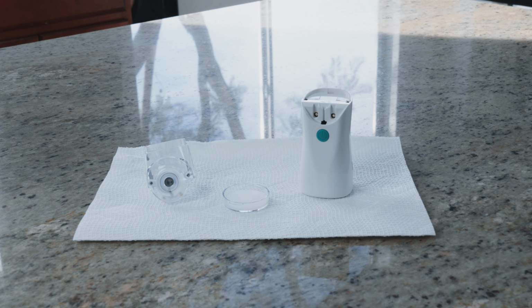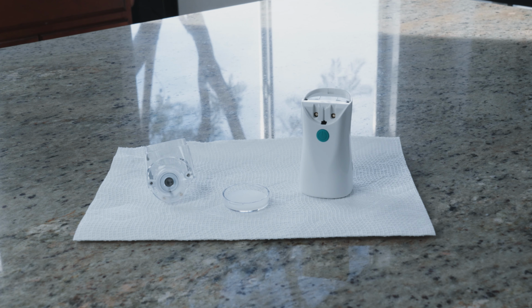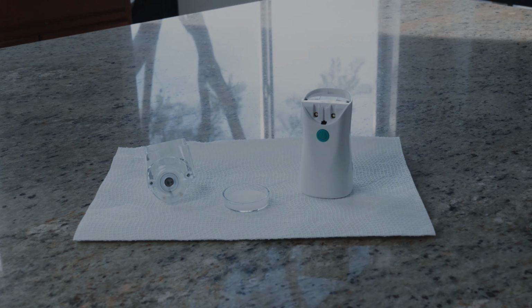Let the unit air dry in a well-ventilated area. Make sure not to use paper towels or tissues to dry any remaining moisture. These materials can leave particles or residue. It is okay to use medical gauze to wipe away moisture if you prefer, again, avoiding any contact with the mesh plate. Make sure that the reservoir sits for long enough to completely dry. Do not put away or store your nebulizer if there is any moisture present.